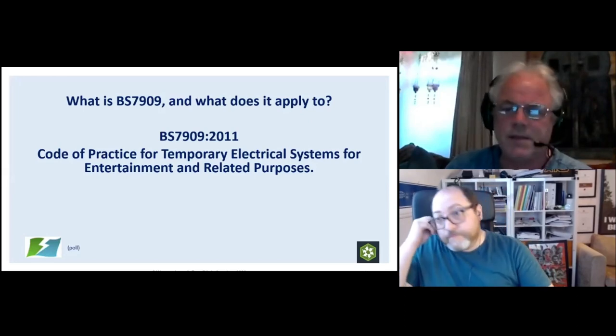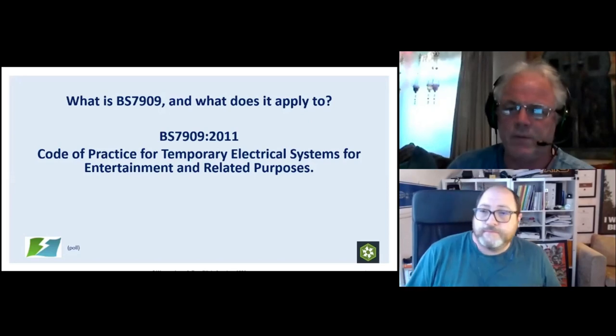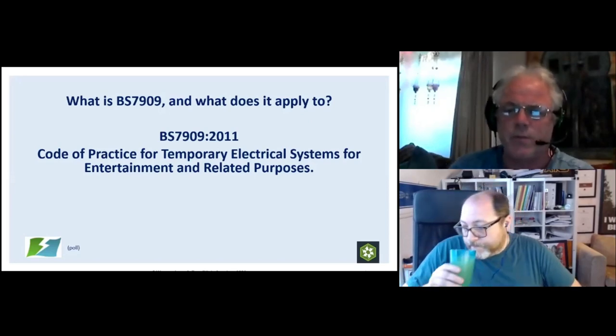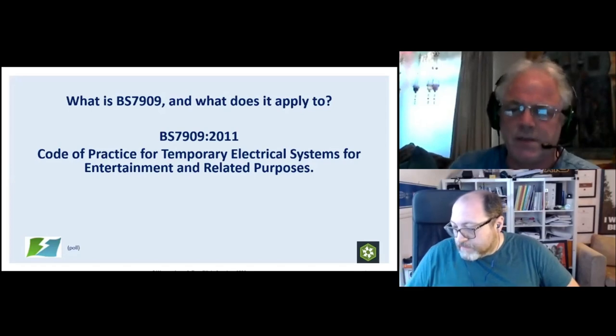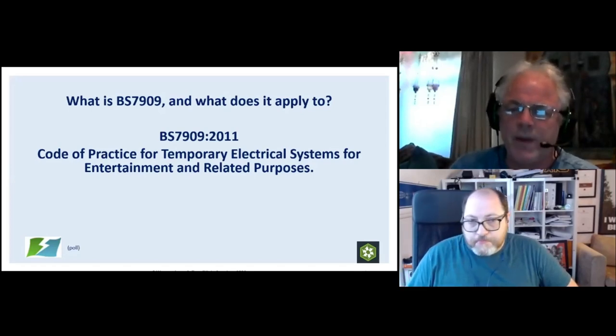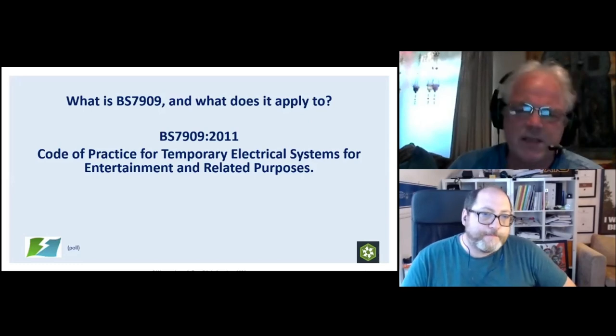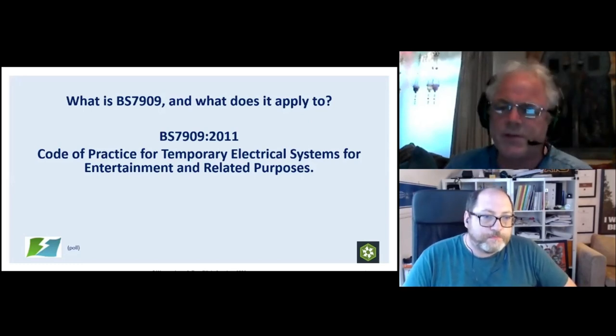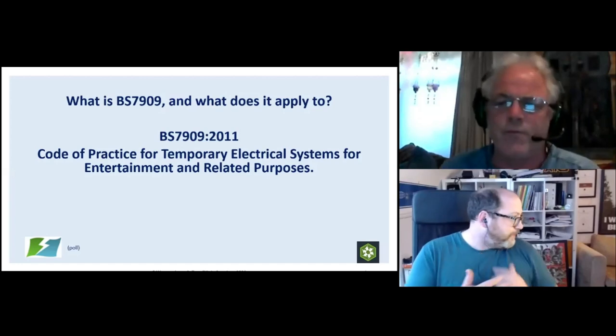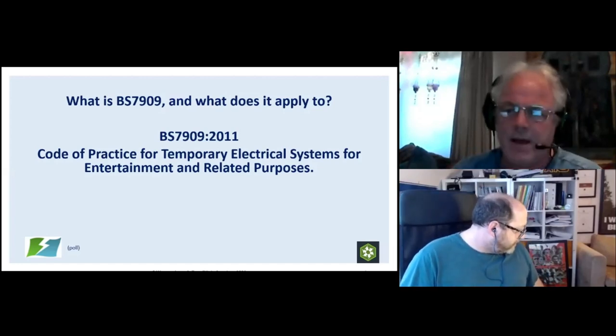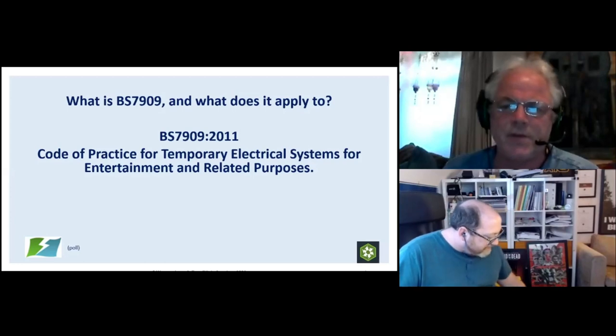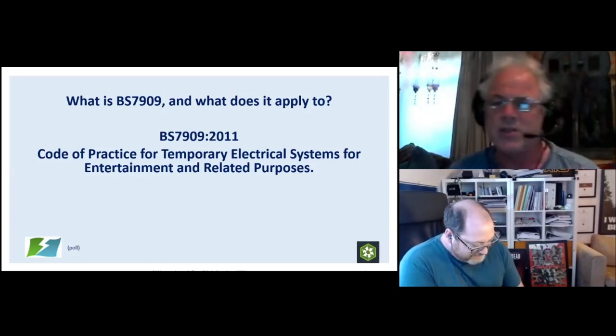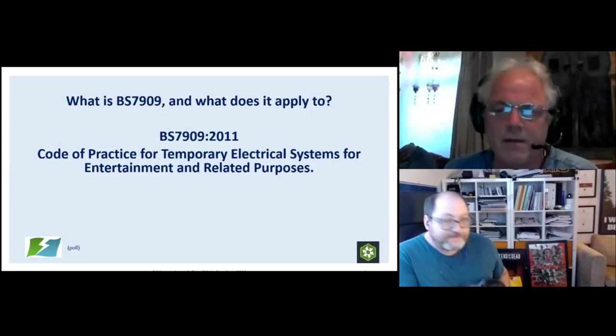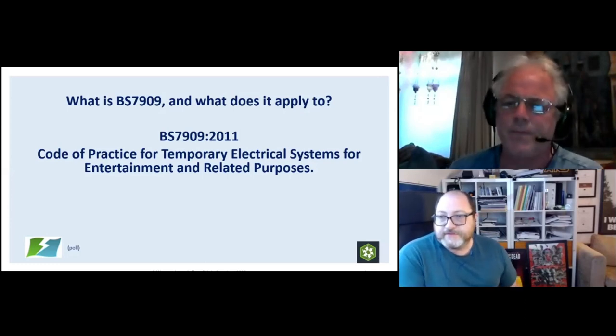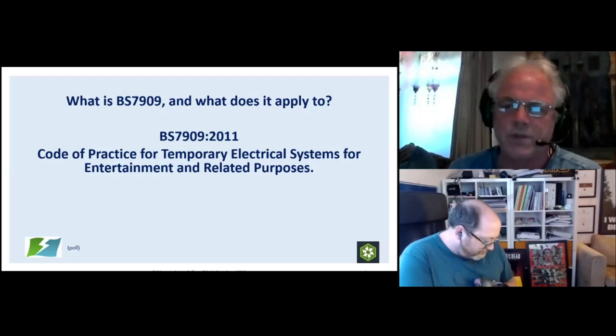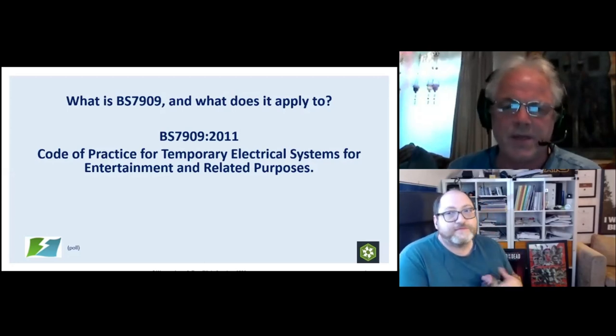Yeah, there are certain things that we've found due to our experience in temporary systems. When we transferred that over to fixed installations, we found that we were picking up problems in things like fault current, short circuit current, which is an issue with temporary systems because of the length of run. Even though it's not part of the scheduled testing when you go by Guidance Note 3, we found we were picking up faults and issues. So yes, it's been very useful for that as well.